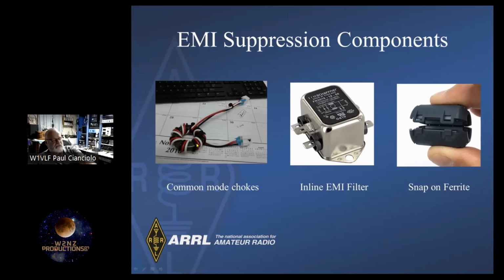Let's say you have this core on the left-hand side, and you place one turn of this cable through it. At the frequency you're interested in, you get 10 ohms of choking impedance. That's not going to do anything. 2 turns will give you 40 ohms. 8 turns will give you 64 times that, so 640 ohms. It's one place in life where you get something for nothing.